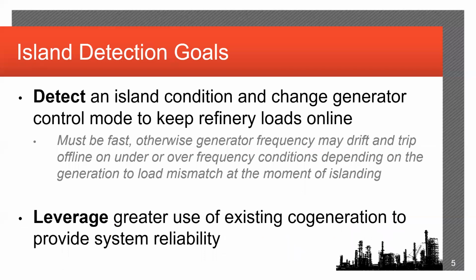So the goals of this entire project are two things. Anytime that the refinery electrically becomes disconnected from the utility, we want to know when that happens and detect it, and then very quickly send a signal over to the turbine generator controls to change their operating control mode such that they can continue to run independently of a connection to the local utility.